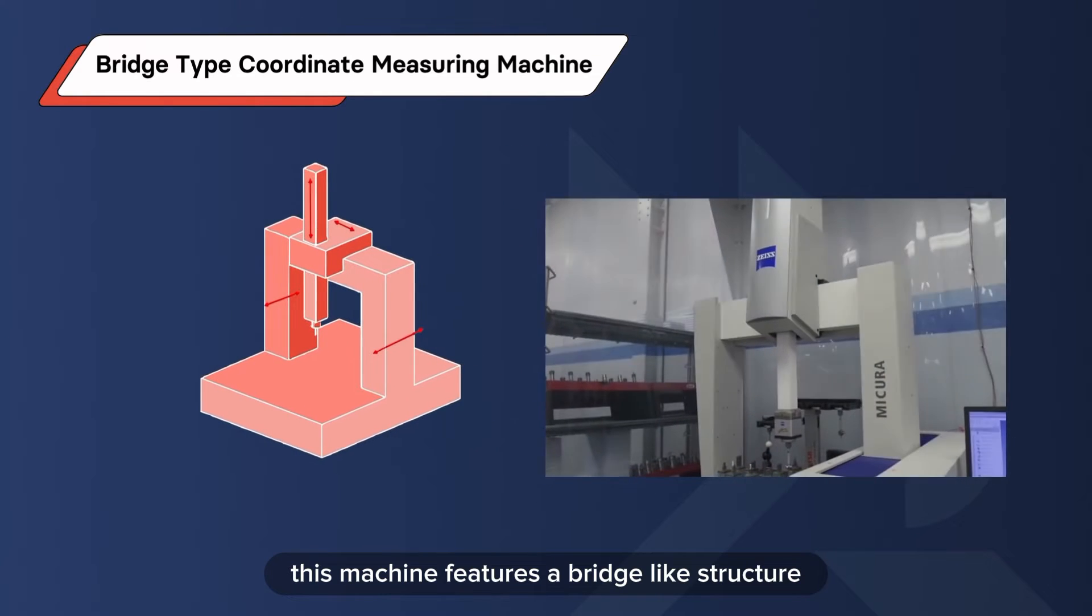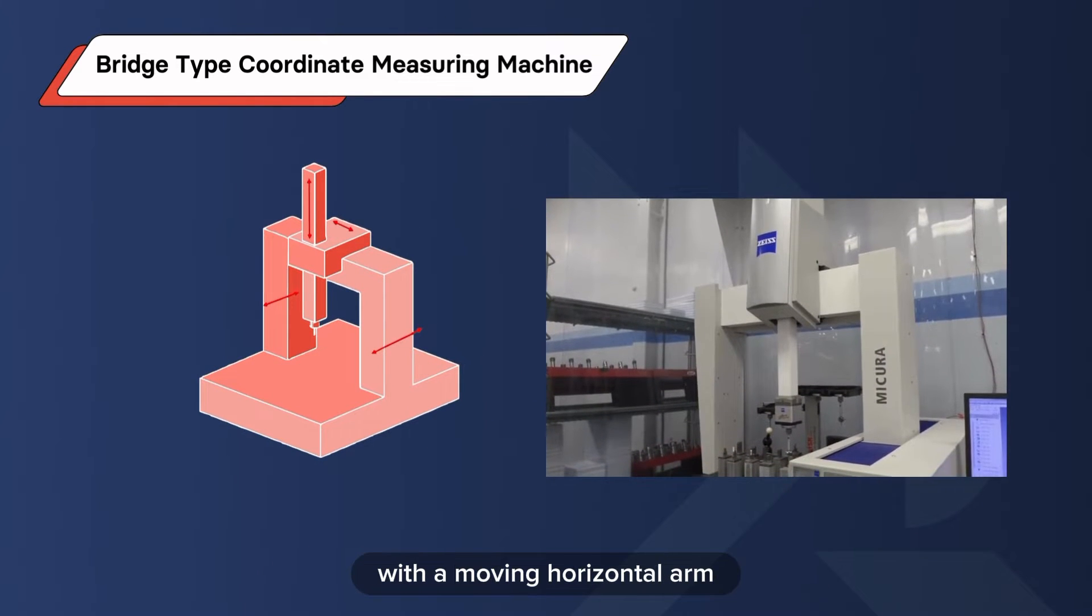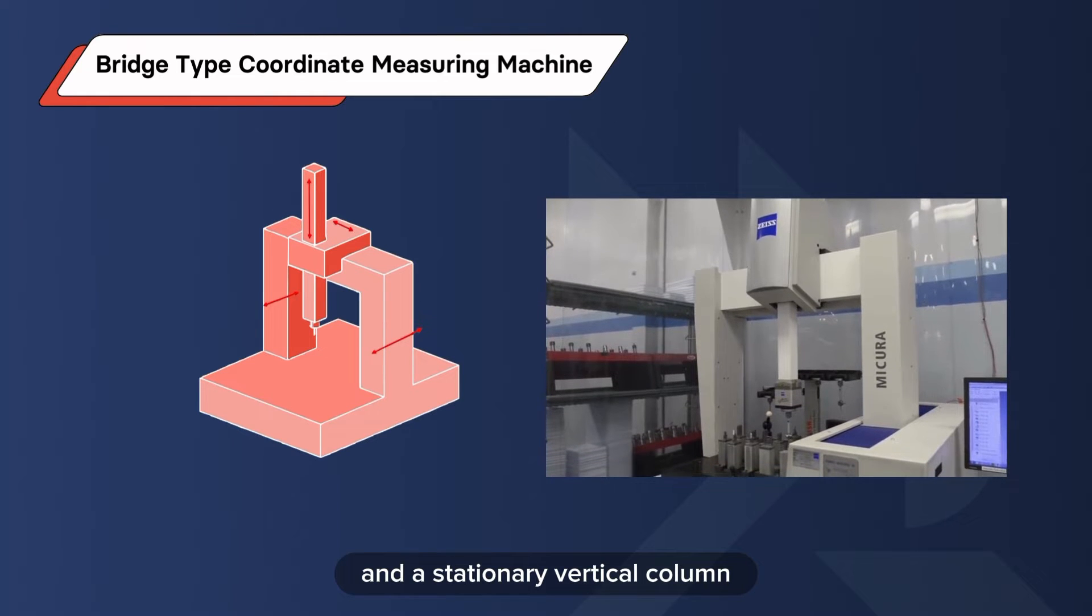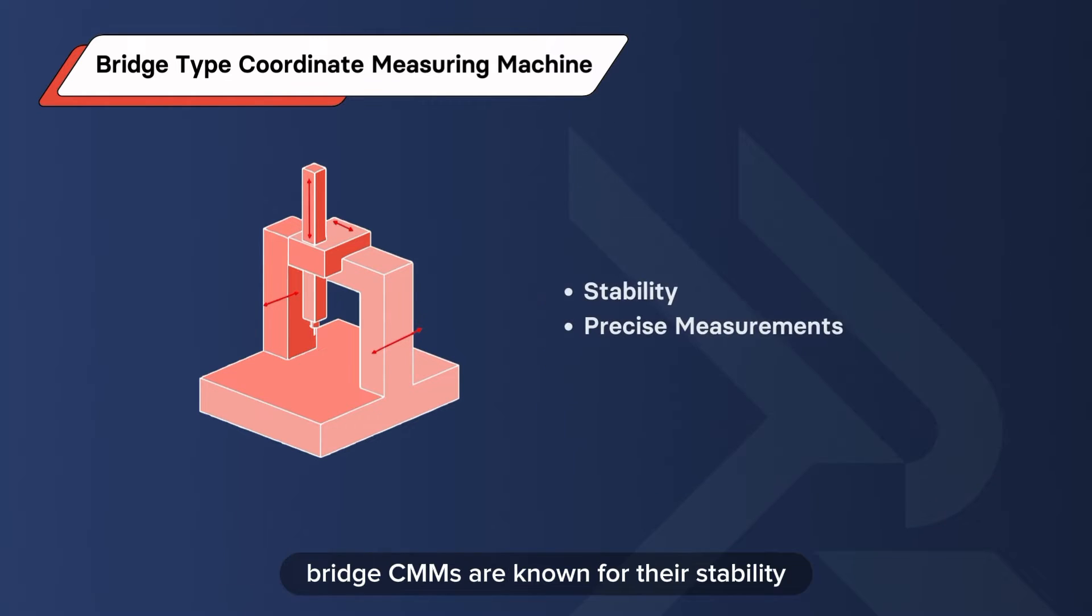This machine features a bridge-like structure with a moving horizontal arm and a stationary vertical column. Bridge CMMs are known for their stability and are ideal for precise measurements.